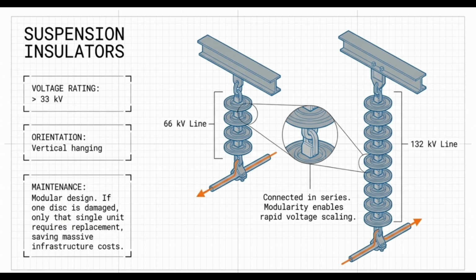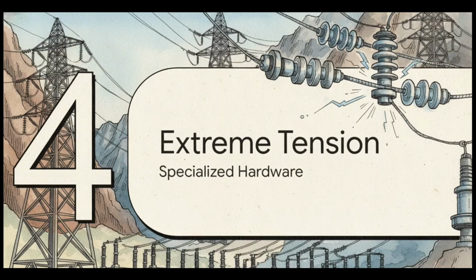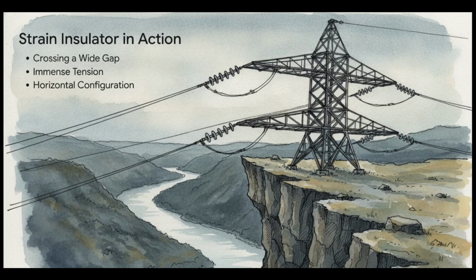It's just brilliantly efficient. Section 4. Extreme tension and substations: specialized hardware. Sometimes physical geography forces engineers to use entirely different configurations. I mean, a power line can't always just go straight, right? When a transmission line reaches a dead end, has to turn a really sharp corner to avoid a mountain, or needs to cross a massive gap like a wide river or a valley, the mechanical tension pulling on that line is absolutely staggering. Standard vertical suspension strings would swing wildly out of control or just snap entirely.